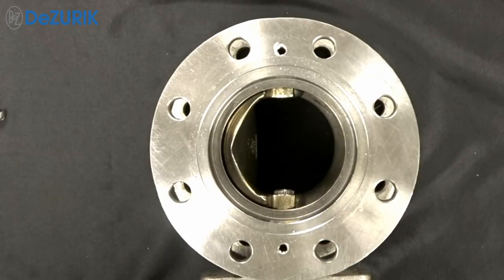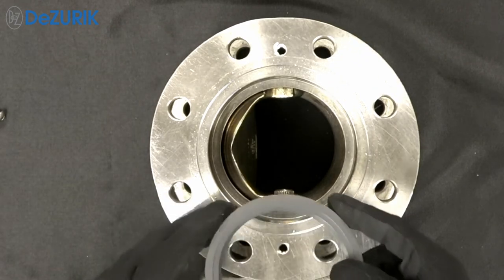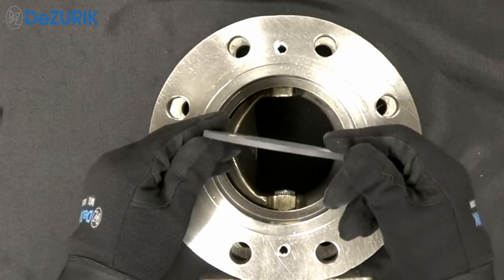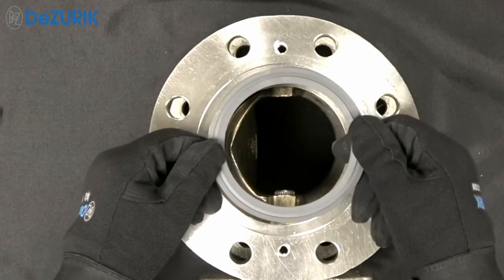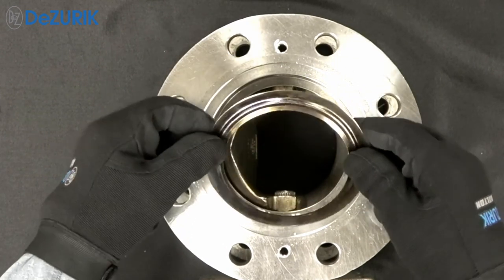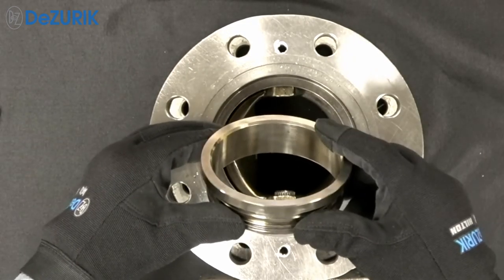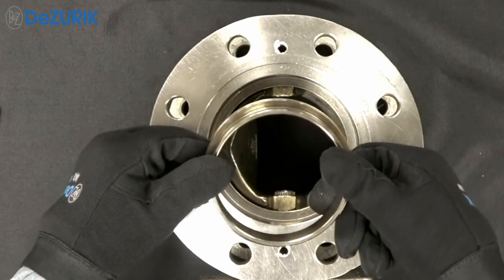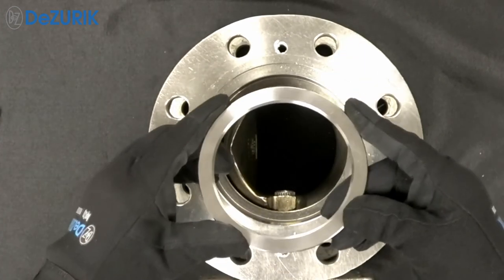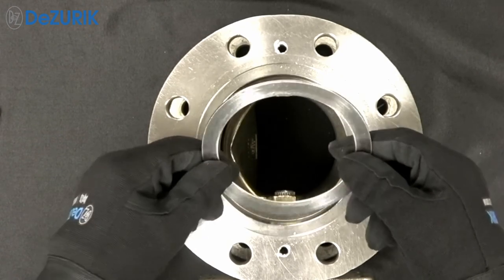The DeZURIK V-Port ball valve is available with four seat options, and all bodies will dimensionally accept all seat options. The reinforced PTFE seat is designed for clean service when tight shutoff to ANSI class 6 is required. The flex metal seat is designed primarily to shear fibrous slurries and provides ANSI class 4 shutoff. The rigid seat is designed for abrasive applications including reclaimed fiber and applications with suspended solids, also providing ANSI class 4 shutoff. The clearance seat is designed for maximum control in applications that do not require tight shutoff.